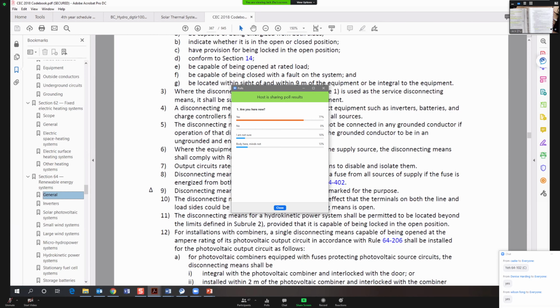Subrule A, a disconnect means shall be provided to disconnect a fuse from all sources of supply. The fuse can be energized from both directions. So if you have a fuse for the renewable energy system, you have to provide the disconnect means on both sides of that fuse. Because normally a fusible disconnect means you can only disconnect a fuse from the supply side. So for the renewable energy system connection, you have to be able to disconnect that fuse to make that fuse dead, because you have a renewable energy system, so your fuse could have power feeding from both sides. That's why you need a disconnect means on both sides.